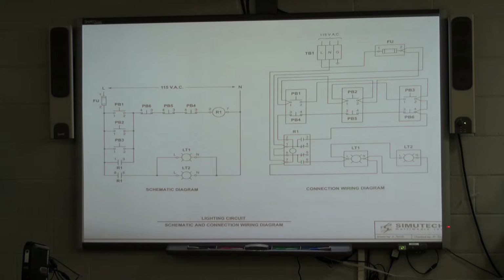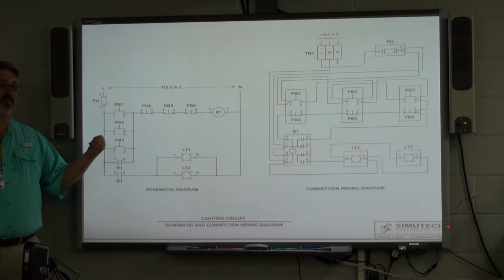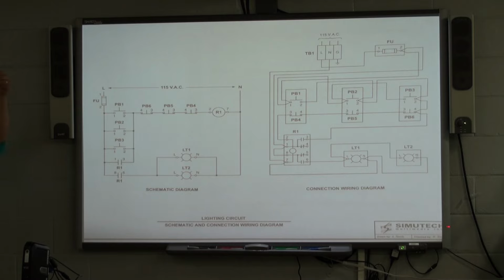So that's how we can latch a relay. The nice part is, if we have a power interruption, as soon as power comes back on, we don't have to worry about this coming back to an on state. The only way it can come back on is if we press a button to set it. So as soon as we lose power, either through the utility shutting down or by breaking this circuit, this thing's going to be shut off.